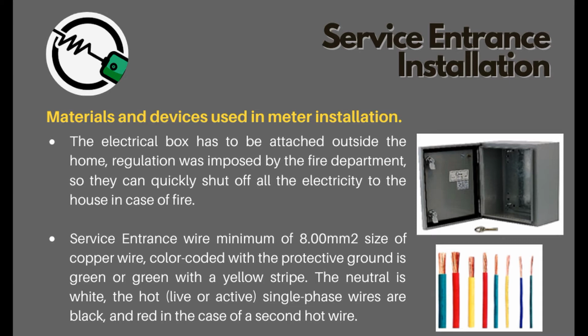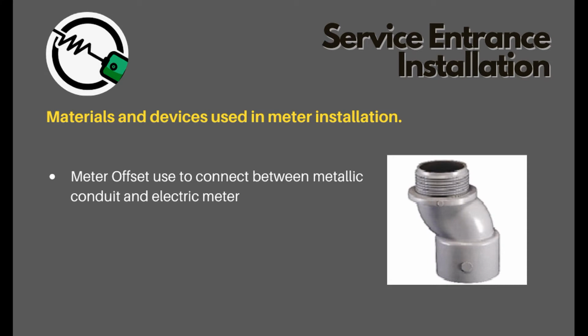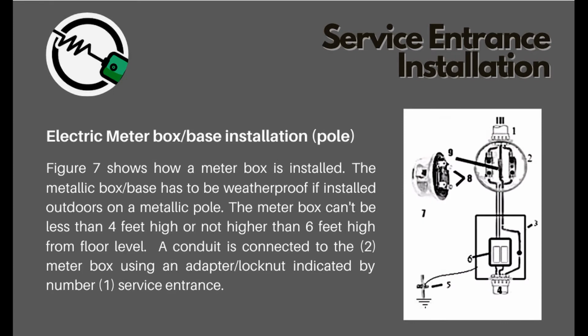The neutral is white, the hot, live or active, single phase wires are black, and red in the case of a second hot wire. Meter offset: used to connect between metallic conduit and electric meter. Electric meter box, base installation, pole. Figure 7 shows how a meter box is installed. The metallic box base has to be weatherproof if installed outdoors on a metallic pole. The meter box can't be less than 4 feet high or higher than 6 feet high from floor level.